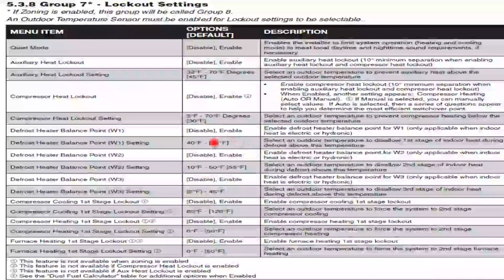If we have 3 stages of heat strip, we can actually lock out each stage of heat strip. So we could say we only want the 5 kW to come on at 40. We want 10 kW to come on at 10 degrees, and then at 5 degrees, we get all 25 kW of heat strip. So if we do have an energy conscious homeowner, we can actually save them a little bit of power. They lose some comfort, but they're saving electricity. We can do that with the furnace heating also, and the compressor heating.